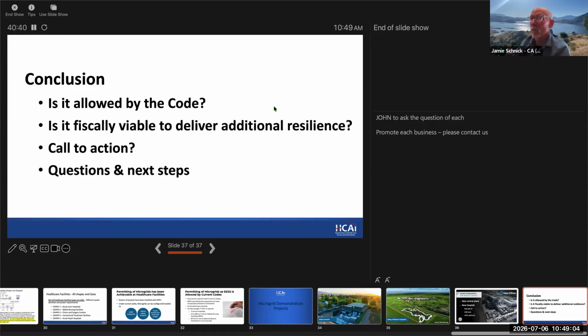And one of the great benefits that we hear from Kaiser is that now they don't have to reschedule surgeries. Now they don't have a real outage condition because nobody knows. Basically, the requirement to have two sources always available for emergency power, as a minimum requirement to continue surgeries as normal, they meet that criteria by virtue of the microgrid.